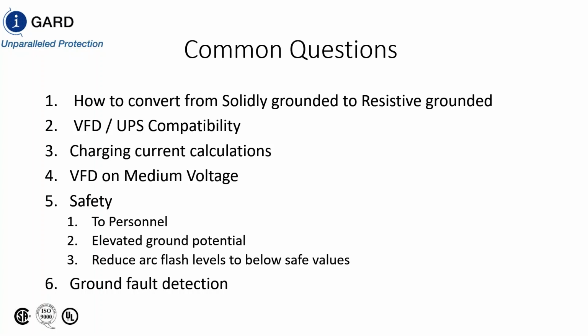So if you're in a hospital and one of your breakers is feeding an operating room, you obviously do not want that to trip. So you're going to set that as the highest priority. So that means if you get a ground fault on B phase of that breaker, and then you get a fault on A phase on another breaker, the breaker that is servicing the A phase fault will trip first, and the B phase fault that's feeding the operating room will not trip. And if you set it as the highest priority and you have a catastrophic problem, it will always be the one that's in service. Similarly, if you have a data center, chillers and air conditioning units are very important, so they will always have a higher priority.